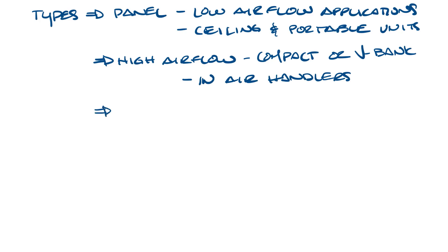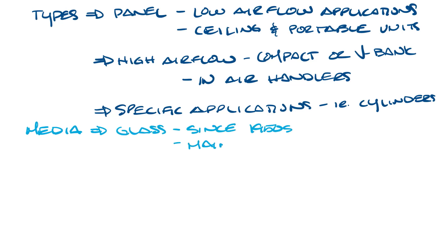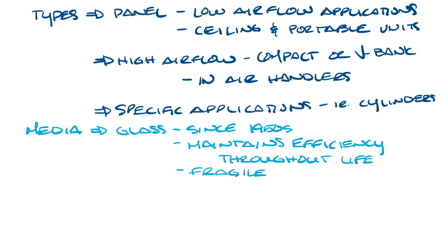And then there are HEPA filters that are tied to specific designs or installations, like cylindrical HEPA filters. There are three basic filter medias that you will see used. Glass fiber, which has been used since the 1950s, maintains its efficiency throughout its lifetime, but it's fragile and can easily be damaged, possibly creating holes where the filter isn't as effective.